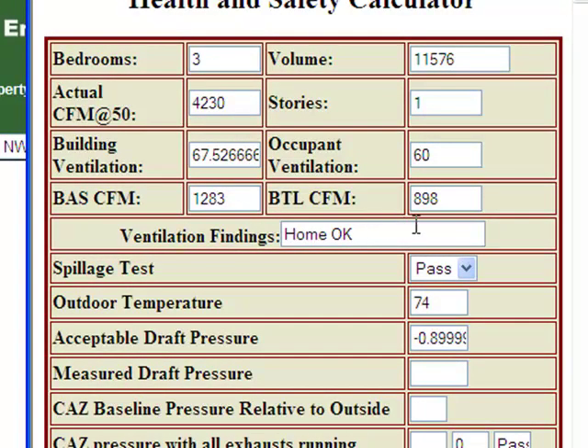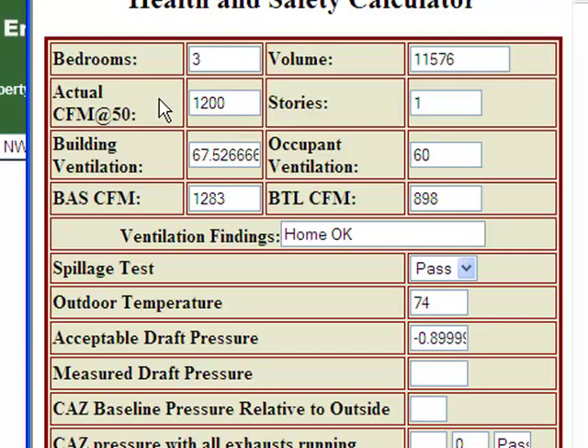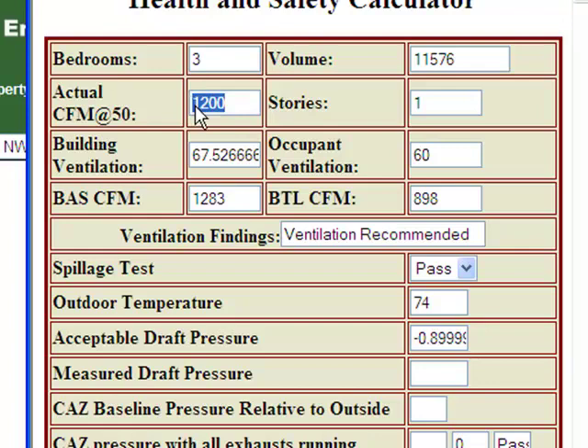The building tightness limit of 898 is calculated as 70% of the building airflow standard. If our actual CFM 50 had been lower than the building airflow standard but higher than the building tightness limit — let's say 1,200 CFM at 50 pascals — the ventilation findings would say that ventilation is recommended. If we had a very tight home and gotten below the building tightness limit, the ventilation findings would tell us that ventilation is required prior to any further air sealing.